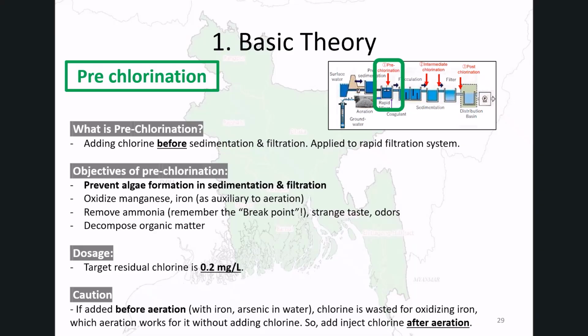A very important caution is shown here. If chlorine is injected before aeration in water containing iron, chlorine is wasted for oxidizing iron. Aeration can do this oxidation without using chlorine. Therefore, pre-chlorination should be applied after aeration, not before.